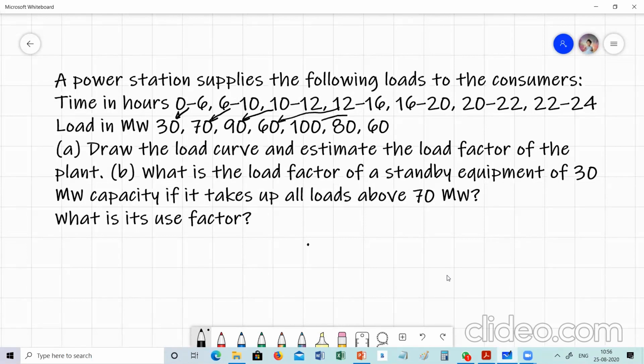From 16 to 20 - 16 means 4pm, 20 means 8pm - the load is 100 megawatt. From 20 to 22, the load was 80 megawatt, and from 22 to 24, the last 2 hours, the load was 60 megawatt. So they ask to draw the load curve and estimate the load factor of the plant. Second, what is the load factor of a standby equipment of 30 megawatt capacity if it takes up all loads above 70 megawatt? What is the use factor? They are asked to calculate various factors.